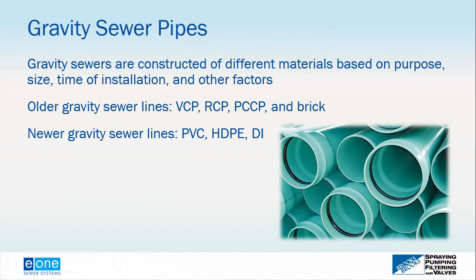Gravity sewer pipes and low pressure sewer pipes are constructed of similar materials, primarily based on the era of installation. Older gravity sewer systems may use vitrified clay pipe, reinforced concrete, pre-stressed concrete, or brick pipe. Some very old large sewers in northern territories were even built from tree trunks. Modern gravity sewer systems are typically constructed of polyvinyl chloride (PVC), high-density polyethylene (HDPE), or ductile or cast iron — and PVC and HDPE are also commonly used in low pressure sewer systems.